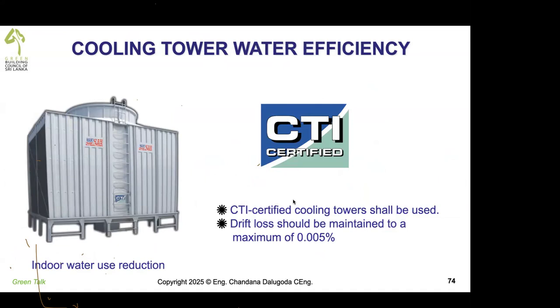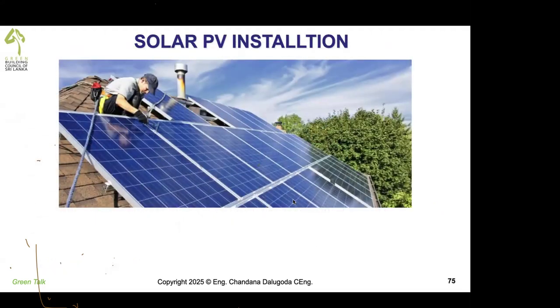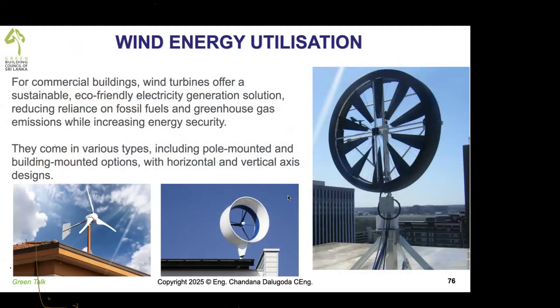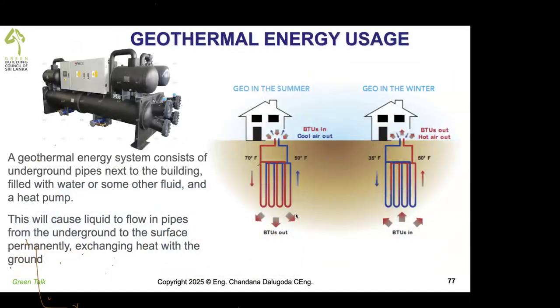Cooling tower water efficiency. That is, you'll have to use a cooling tower with CTI certified, especially those cooling towers, drift loss, that is water carry over by air, drift loss. Water carry over by air, drift loss, has to be kept 0.005% and below. Then we minimize water usage, water saving by that way. Solar PV installations, definitely there is a common thing nowadays in houses. Wind energy utilization. Yeah, when we say wind energy, we remember large wind farms and wind tunnels. No, these smaller wind turbines are available. And geothermal energy. Now, this is for a very large building complex.